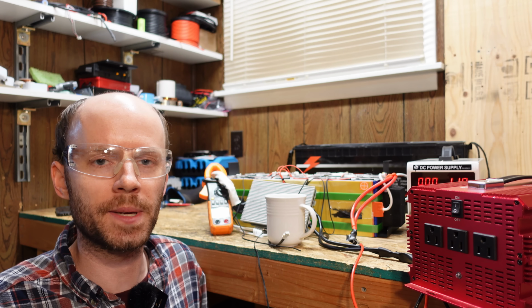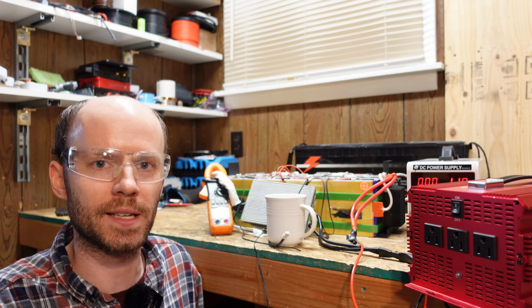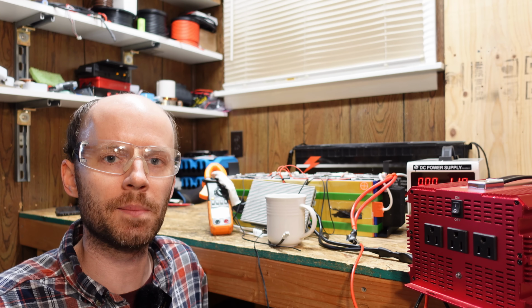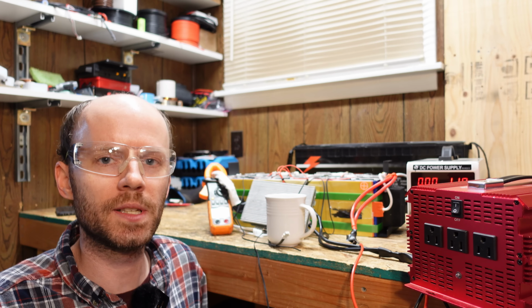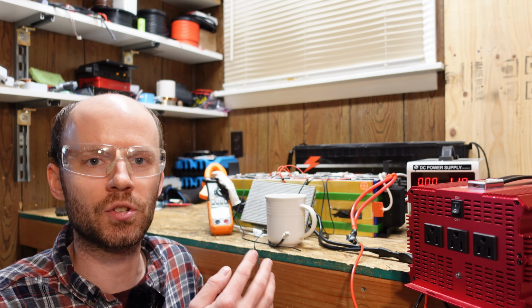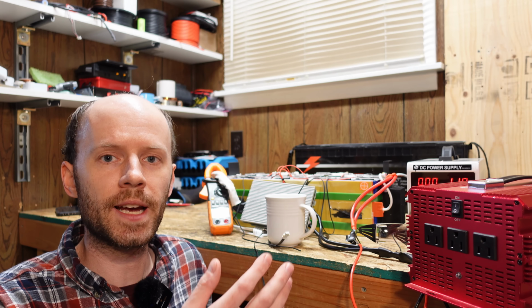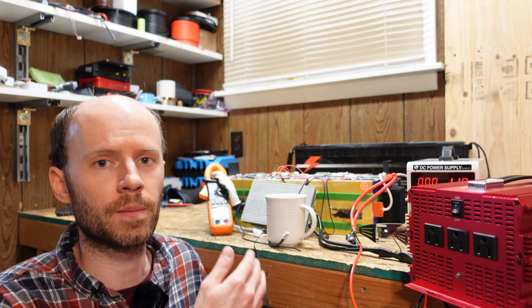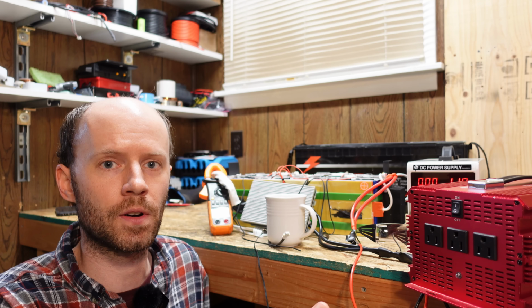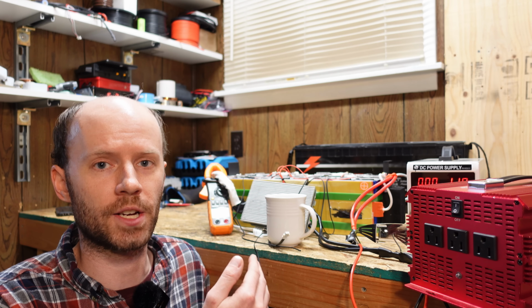So I can trigger the BMS low voltage disconnect in many of my tests with this inverter. As you saw with the MPP solar inverter, its low disconnect is a bit higher, so I wasn't able to trigger the BMS disconnect with it. When you connect your inverter to your battery, you'll typically use a resistor to avoid the inrush of current from the battery charging the capacitors in the inverter, which could trip the overcurrent protection of the BMS.